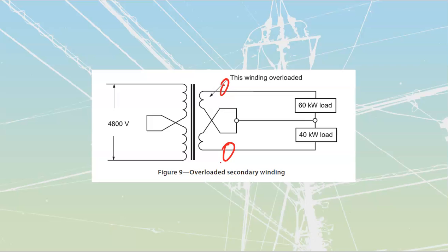You should never have a panel where you've got loads of current coming out of one leg and hardly anything coming out of another leg. It is guaranteed to run you into problems if we have something like that. This is an overloaded transformer because I've got a 60 kilowatt load, and the only path for that 60 kilowatt load to take its current through is that transformer over there. Can we develop 100 kVA of power through this transformer? Absolutely, we can develop 100 kVA of power through that transformer. But this winding right over here is going to be overloaded. We need to balance these loads.